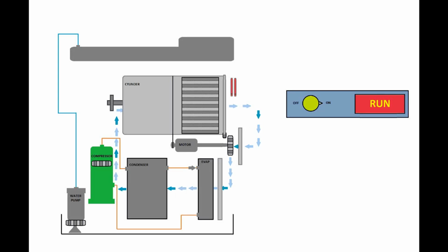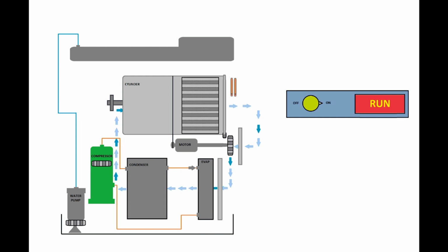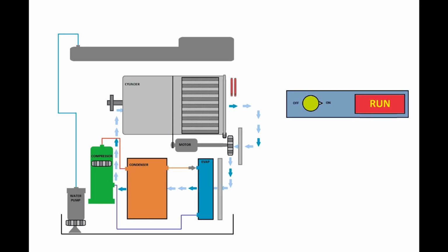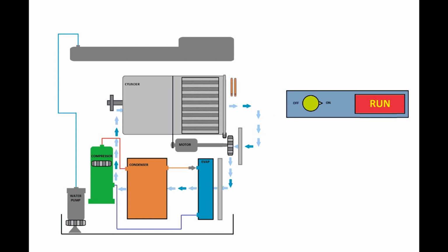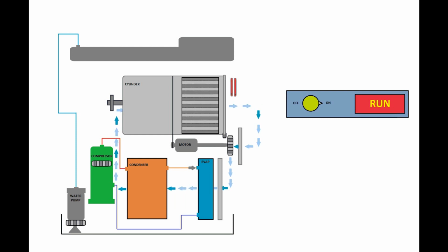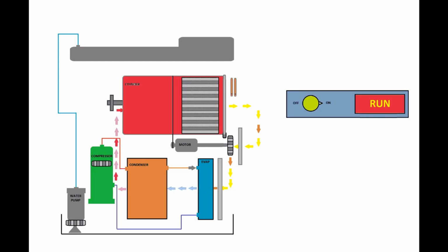Now the compressor starts to work. So see, now the compressor, which is painted in green, is starting, and this is a kind of refrigeration and air conditioning process, but the heat is recovered within itself. I'll explain to you how it works. So now you see the evaporator on the right hand side, painted in blue, is getting very cold, and the condenser in the middle, which is orange in color, is getting hot. This is like a refrigeration process, but you don't get rid of the heat outside. You need that heat, and I'll explain to you why you need that heat. Now, after you start this process, you see the air which circulates inside the cylinder.